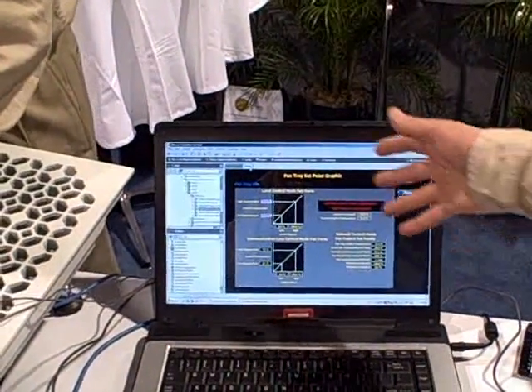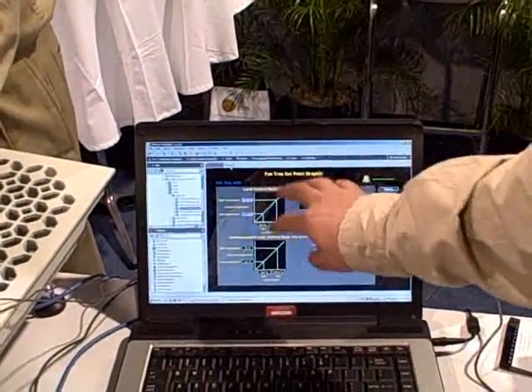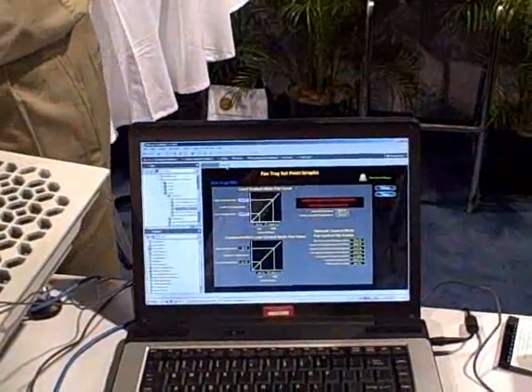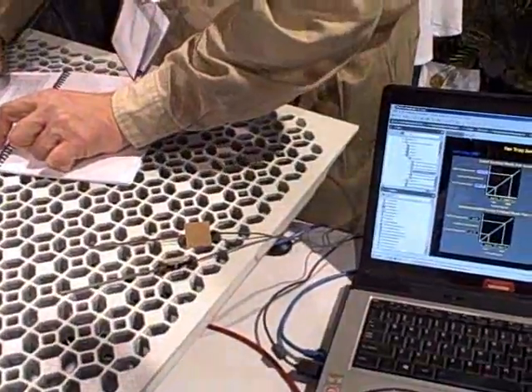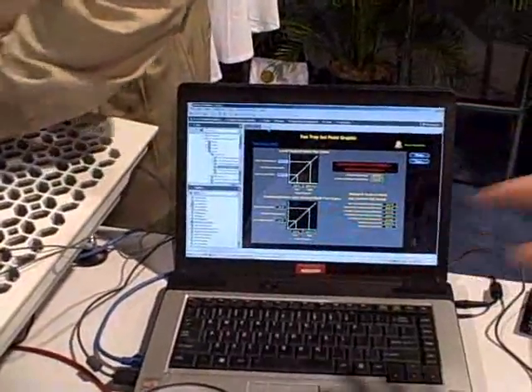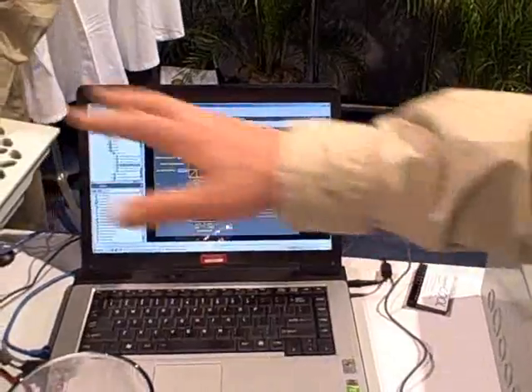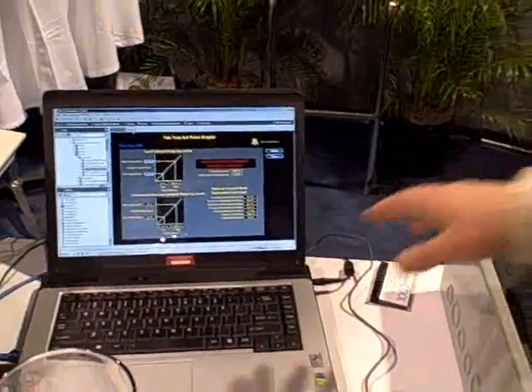On this screen we have the settings for the fan tray, and at this level we have three tiers of control. Local control is where everything is operating right now — it gathers its own thermal information and the onboard intelligence controls the fan to speed up for warmer temperatures and slow down for cooler. If it were to lose communication with the monitor, the fan tray can respond differently — perhaps pushing to near 100% for a critical rack. Finally, in network control mode, the monitor takes over so that fan trays in the zone can react to problems in other zones.